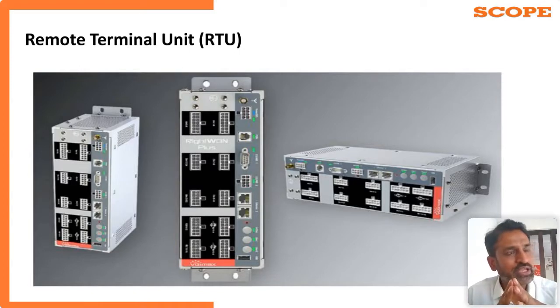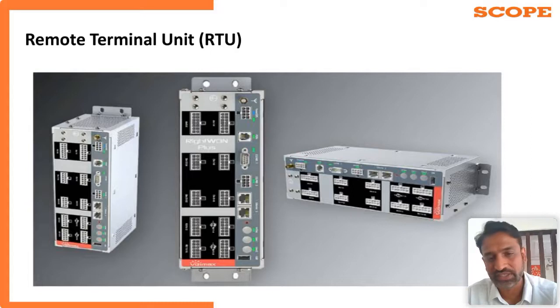But when it comes to this particular topic, we are sticking completely to the automation using the RTU. Why is it important, and what is the difference between the main RTU SCADA system and the automation using RTUs? When you go for a bigger SCADA system, the expenditure involved is high, because you have to connect gateways at the substation using the 61850 protocols, taking the data from all the 61850 protocol relays and sending that data to the control center or substation automation system. These are all very expensive solutions. If you are considering a new substation, maybe that automation system will be helpful.